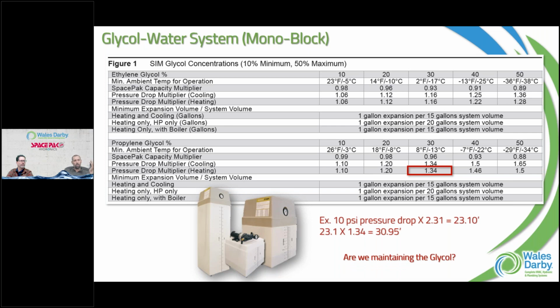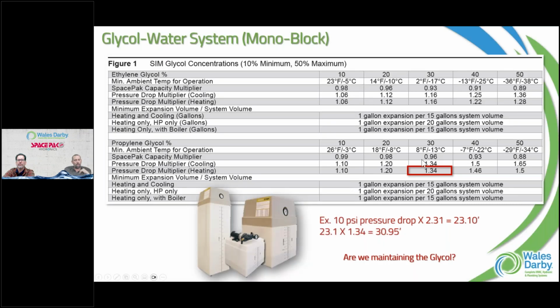So glycol wise, we also have to take into consideration the number above it. 0.96 would be my capacity multiplier. Once I do my load and figure out what the machine's going to do on my design day and see if I cover my load, I might be close there. But remember, the capacity of what you think you're getting out of that terminal unit at a given outdoor temperature and water temp, we have to multiply by 0.96, and that's going to tell us how many BTUs we actually get out of the system. So the more glycol we put in, the bigger the capacity drop.